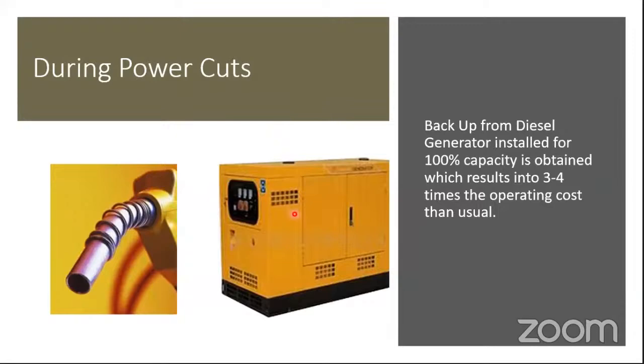Plus, another advantage that thermal energy storage has is during power cuts, for buildings and campuses where the power cuts are frequent, even for an hour or two, running large chillers on DG could be a very, very expensive affair. So if even a backup of those 2 3 hours when the power cut occurs could be planned with the help of thermal energy storage, it could also be a great proposition for saving on diesel generator cost. Plus, when you are able to reduce your chiller capacity, you are also cutting down on your DG requirement.